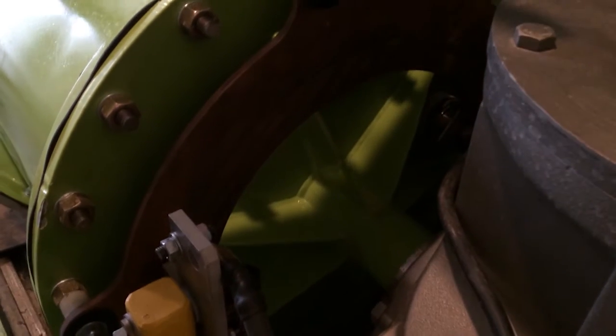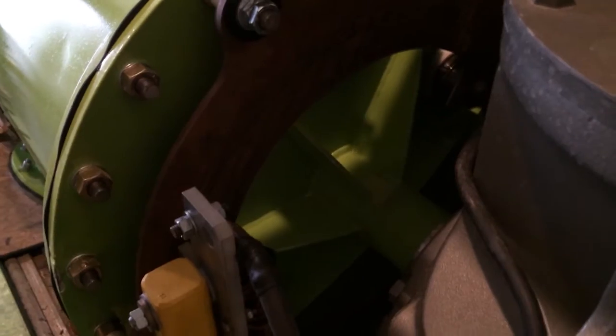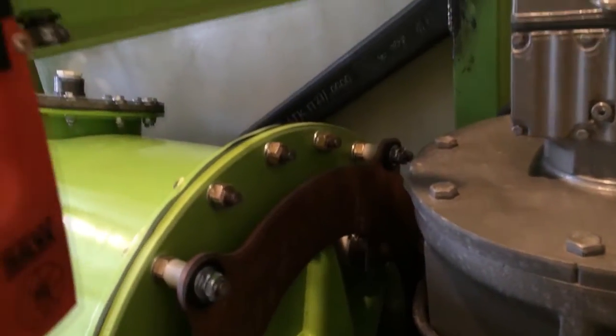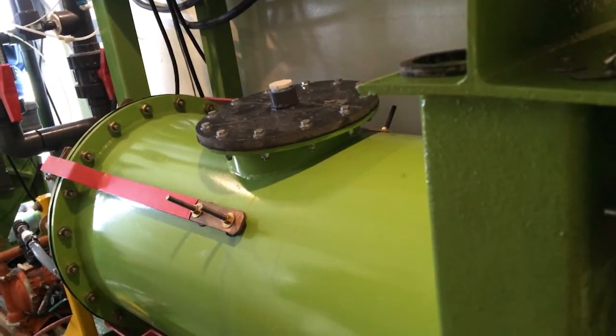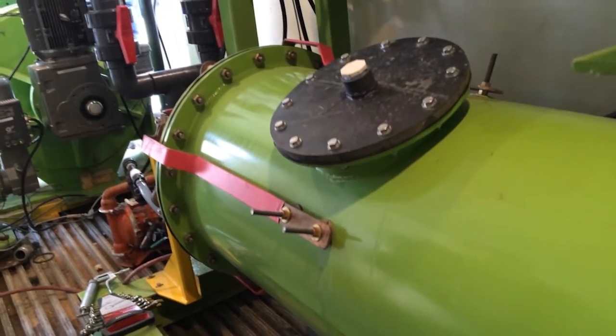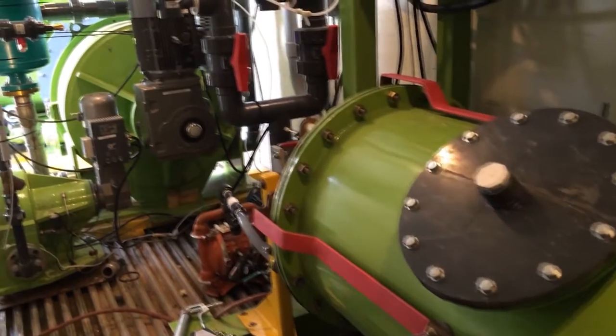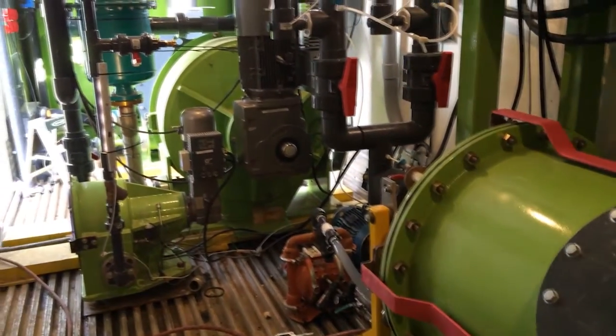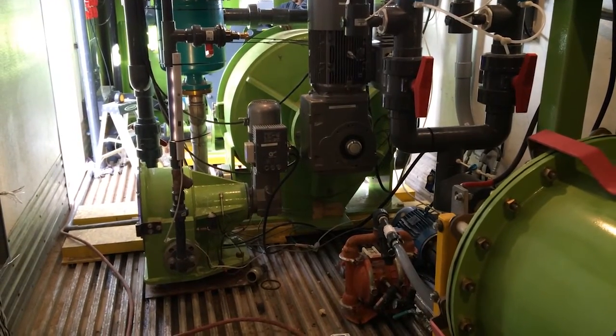In the EC process, suspended solids are attracted to the water with an electrical charge. The process water is flooded with electrons from direct current, passing through the water, which disrupts the charge, allowing the solids to break free from the water molecules. The sacrificial electrode material, which is like small rocks tumbling in a rock polisher, gives off highly charged metal ions, which act like powerful magnets to gather up the solids into clumps.